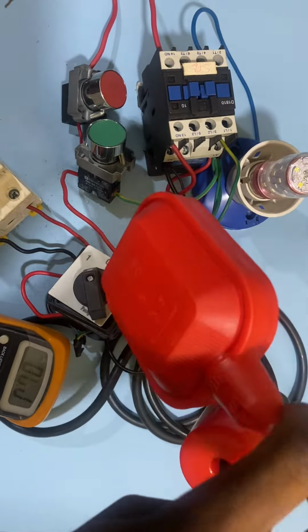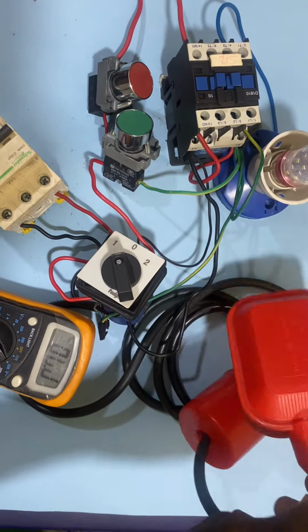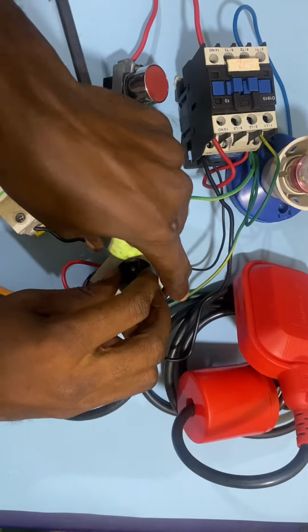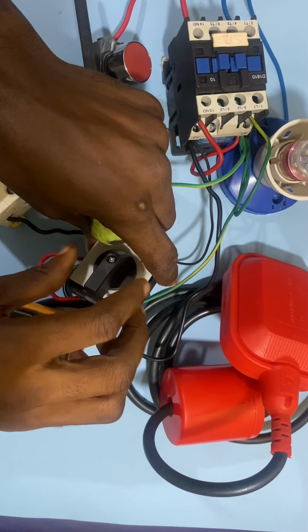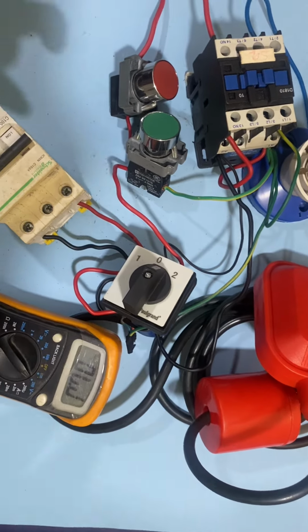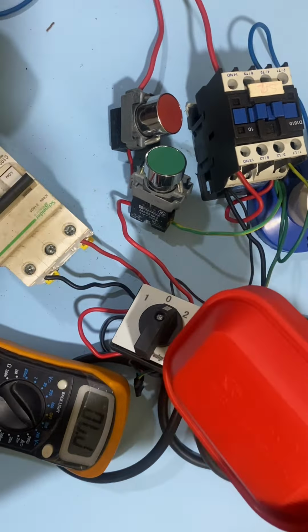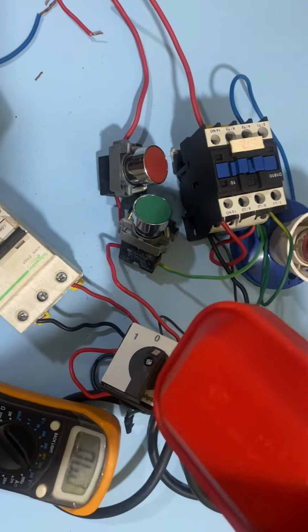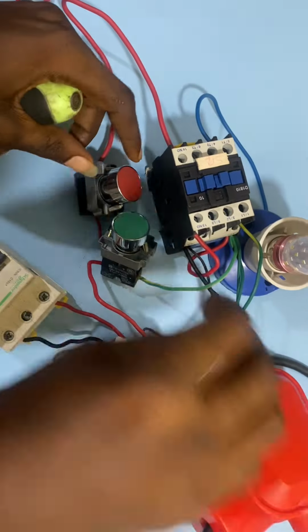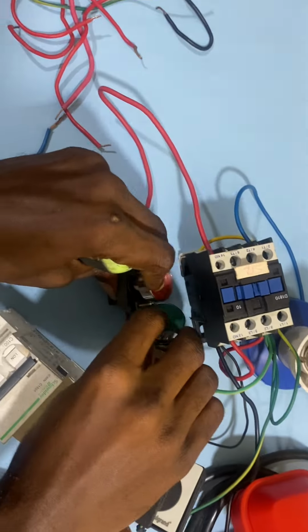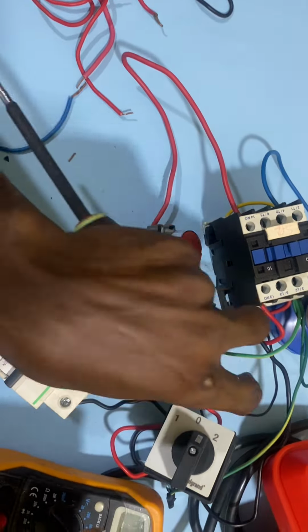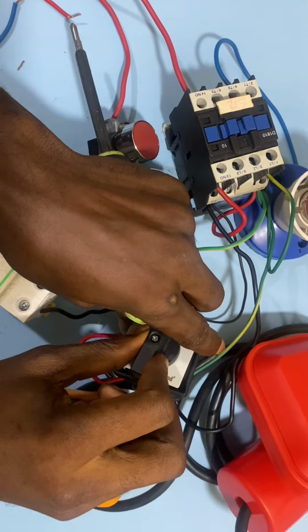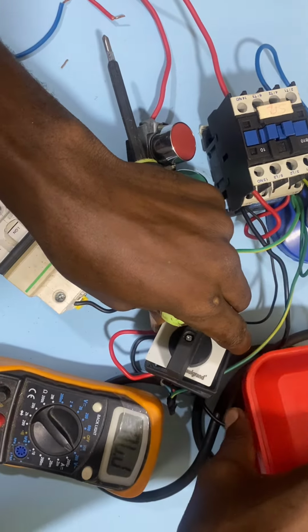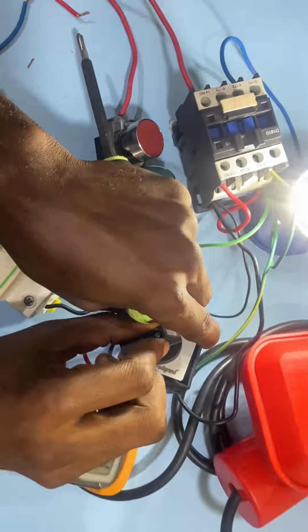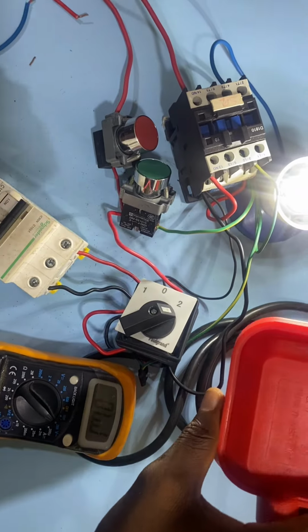So as you can see, the flow switch is not working at that time. Also when you turn the position of the switch to 0, it means that you have isolated the two phases. That means that the flow switch will not pump the water, nor will the start button and the stop button. So as you can see, nothing is working here. So we want to put it at position 2. Position 2 simply means that we are going to use the flow switch to start pumping the water.